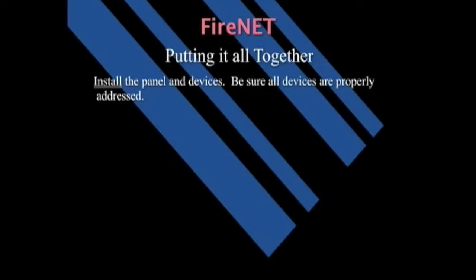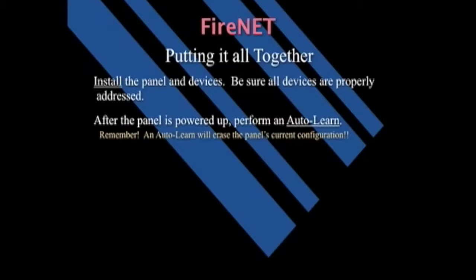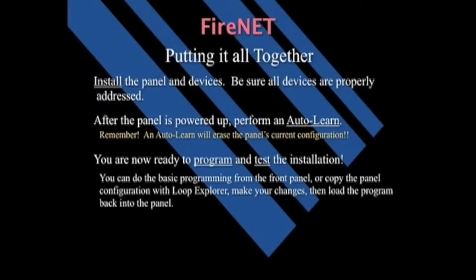Install the panel and the devices. Be sure all the devices are properly addressed. After the panel is powered up, perform an auto-learn. Remember, auto-learn will erase the panel's current configuration. You're now ready to program and test the installation.